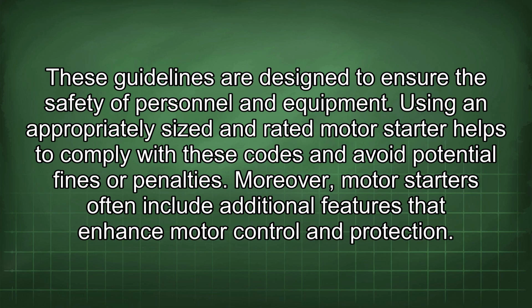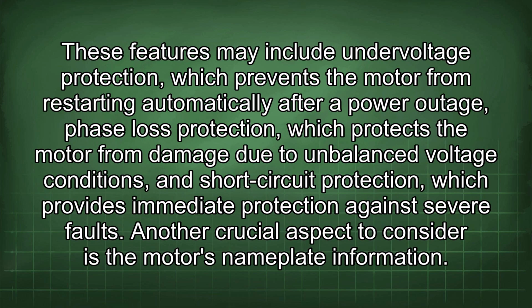Moreover, motor starters often include additional features that enhance motor control and protection. These features may include undervoltage protection, which prevents the motor from restarting automatically after a power outage, phase loss protection, which protects the motor from damage due to imbalanced voltage conditions, and short circuit protection, which provides immediate protection against severe faults. Another crucial aspect to consider is the motor's nameplate information.